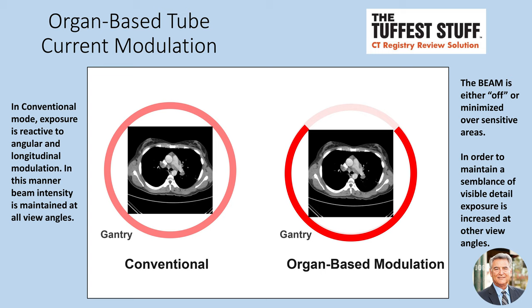The other three types include angular tube current modulation, which is tube current modulation in the X and Y plane, and longitudinal tube current modulation, which is tube current modulation in the Z-axis. The fourth type, in addition to organ-based, is ECG-based or electrocardiogram-based tube current modulation, which is tube current modulation based on some specific point in the ECG.